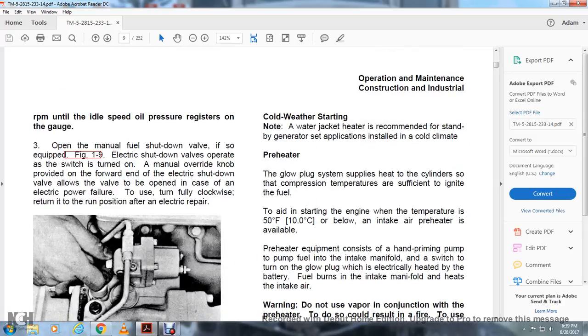Cold weather starting. A water jacket heater is recommended for standby generator set applications. Installed in a cold climate. Preheater. The glow plug system supplies heat to the cylinder so that the compression temperatures are sufficient to ignite the fuel.